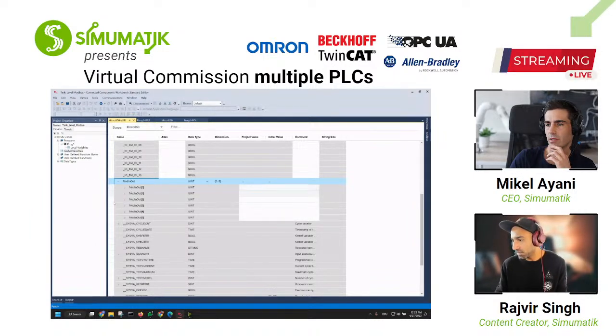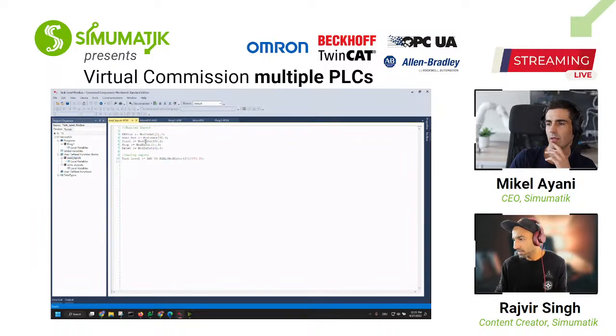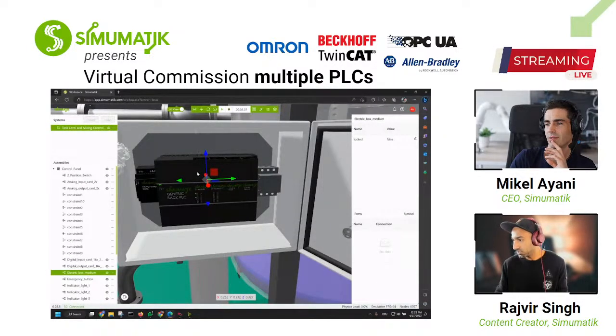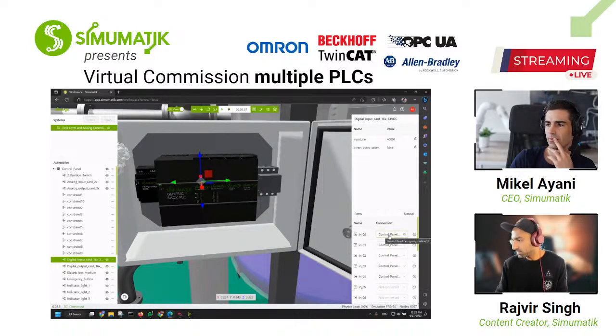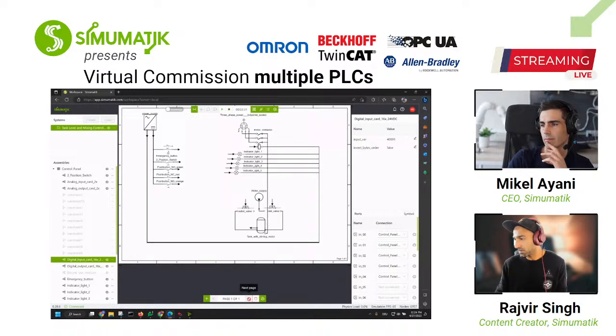And then finally, I map these variables in my program. I have two function blocks, read inputs. Here I'm reading the inputs from mod in out to em stop, second input, auto manual. And how do I know the first input is em stop? Because this is what I connected to my digital input card, the ports. Here you can see, this is the first one, em stop, and then you have toggle switch 14. All the wiring you can also see in the 2D diagram, how the PLC has been wired.